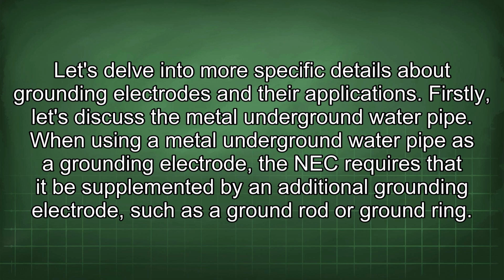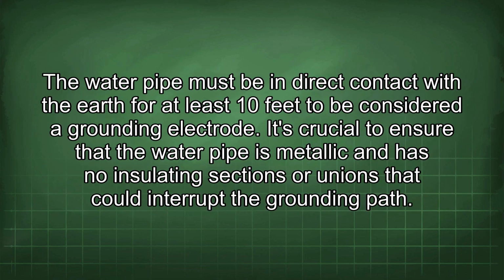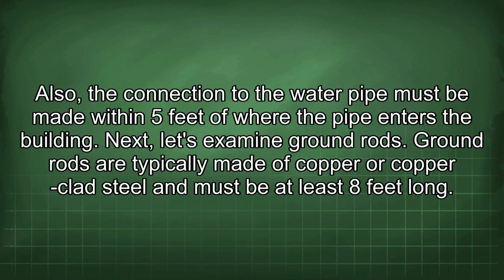Let's delve into more specific details about grounding electrodes and their applications. Firstly, let's discuss the metal underground water pipe. When using a metal underground water pipe as a grounding electrode, the NEC requires that it be supplemented by an additional grounding electrode, such as a ground rod or ground ring. The water pipe must be in direct contact with the earth for at least 10 feet to be considered a grounding electrode. It's crucial to ensure that the water pipe is metallic and has no insulating sections or unions that could interrupt the grounding path. Also, the connection to the water pipe must be made within 5 feet of where the pipe enters the building.